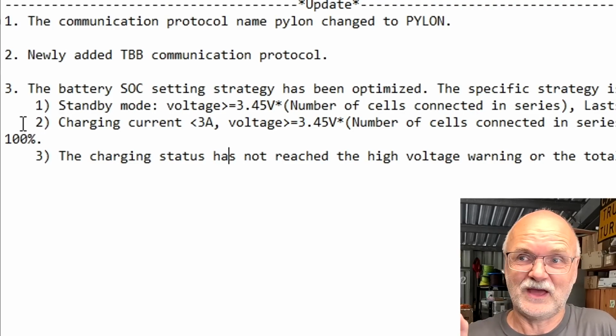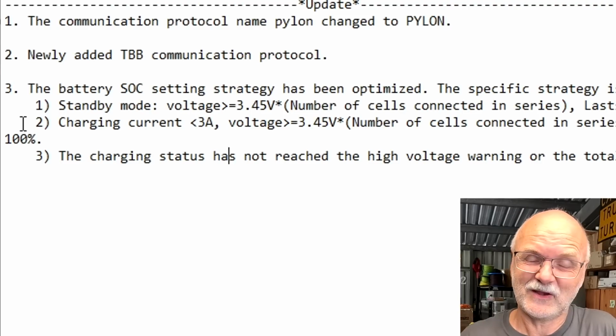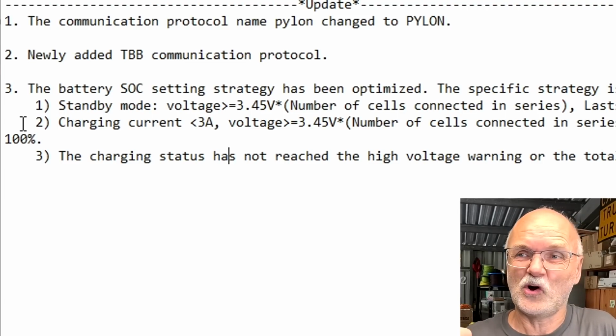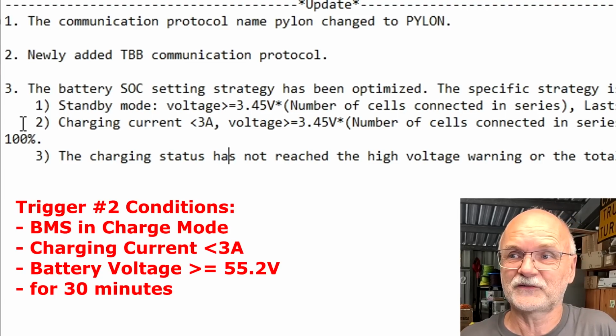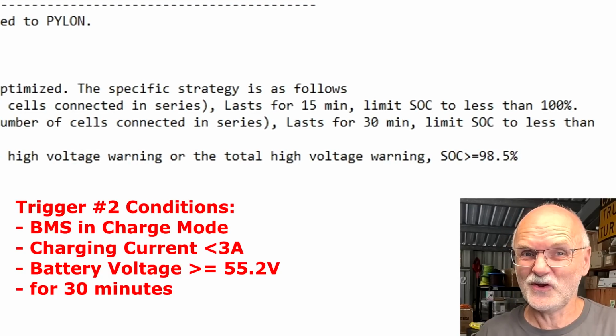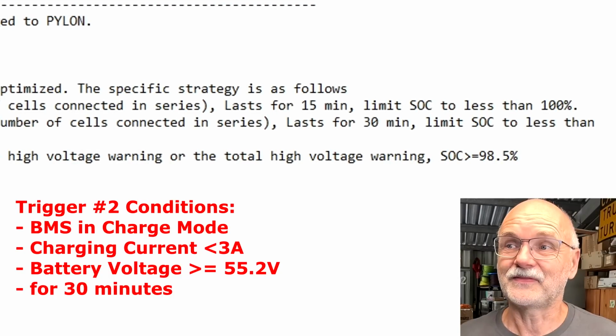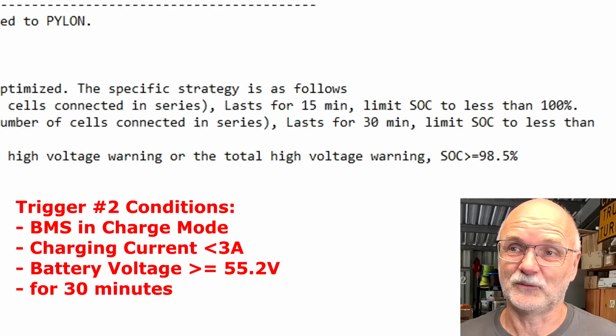Second possibility: charging current smaller than 3 amps, and the battery voltage is again equal to or larger than 55.2 volts. This lasts for 30 minutes, and then it resets the BMS to 100% as well.